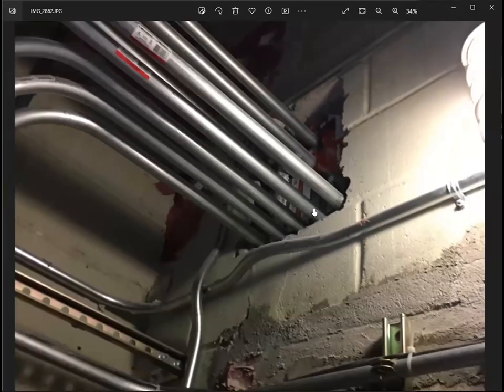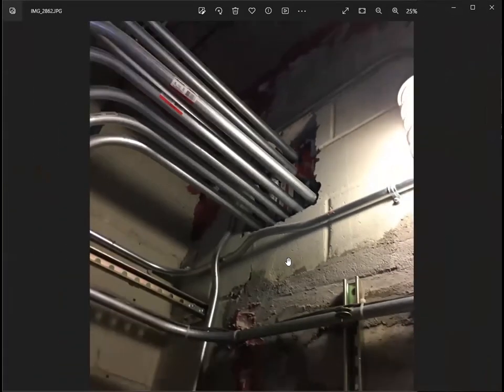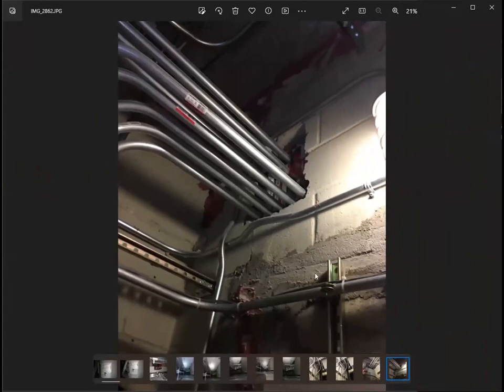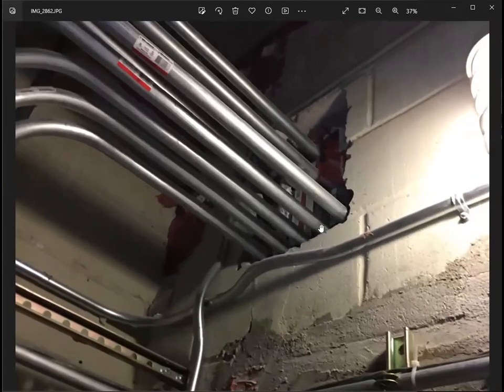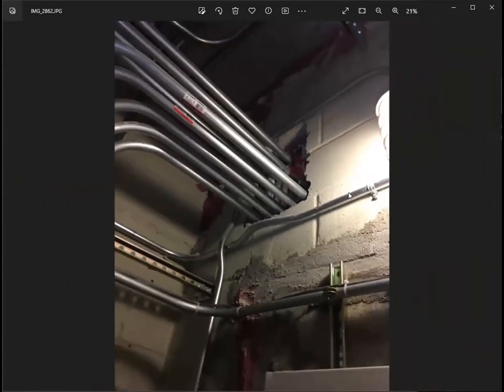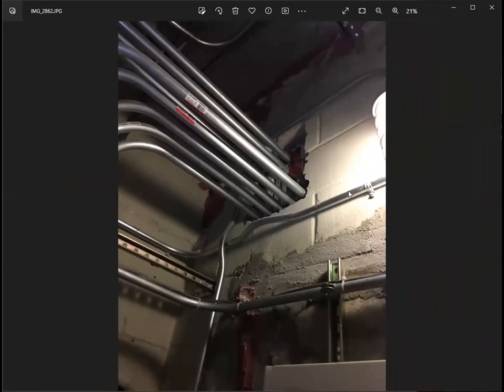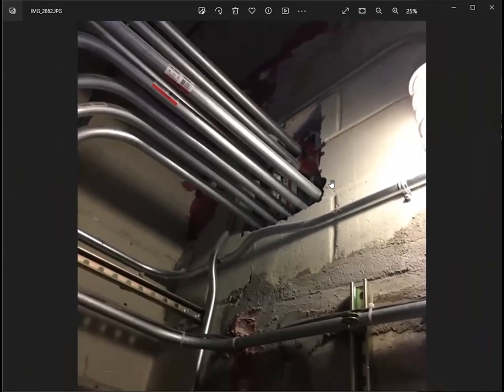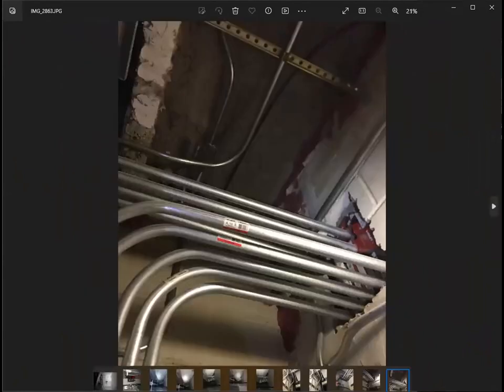Well, same stuff right here. They broke the wall. It's a fire-rated wall, I believe. Probably this room is a mechanical room. Usually a mechanical or electrical room has fire-rated enclosure walls. So everything that you make an opening in like that should be restored to its existing fire rating.